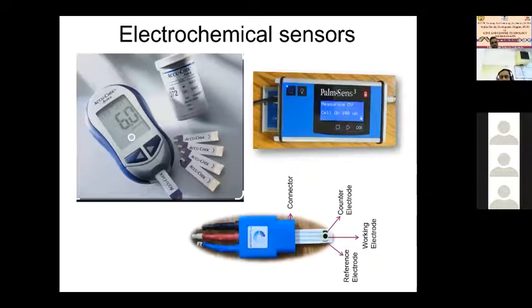That's why it has a wide range of frequencies and other calibration ports. This is the connector point, and we have attached our electrode, similar to the strip here. The central dot is the working electrode, and then there are the counter and reference electrodes. So this is the 3 electrode system.